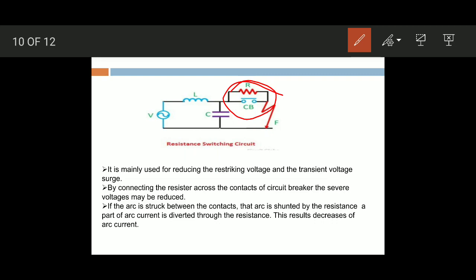If an arc is struck between the contacts, the arc is shunted by the resistance. When the fault is obtained, the circuit breaker contacts are opened. In that case, an arc is struck between these contacts. Then that arc is shunted by this resistance. A part of the arc current is diverted through the resistance also, resulting in a decrease of the arc current. It is used for reducing the restriking voltage and transient voltages, and by using this we reduce the severe voltage drops.